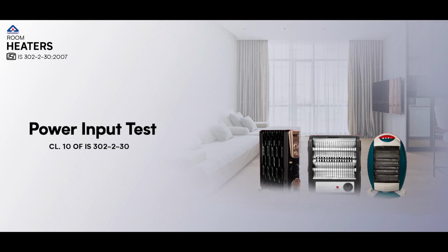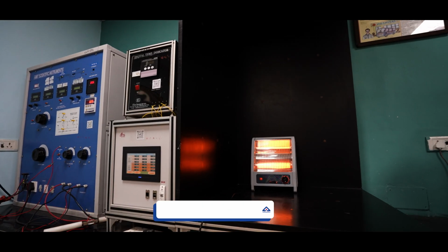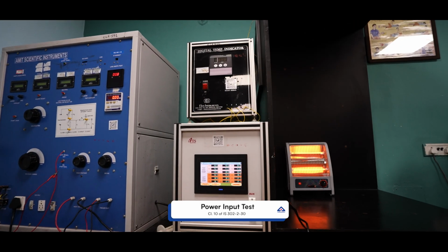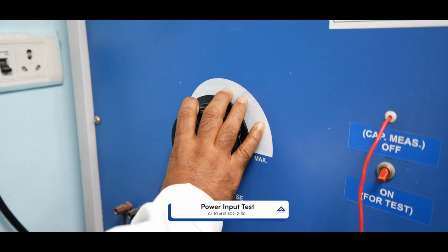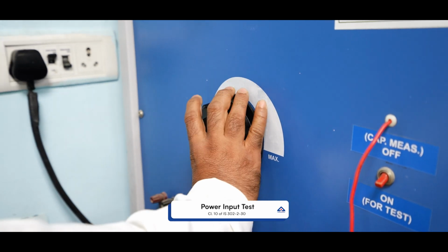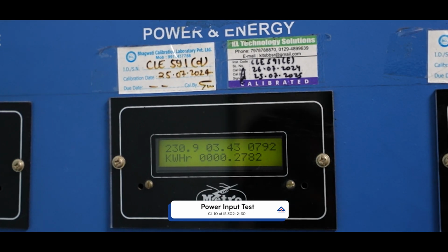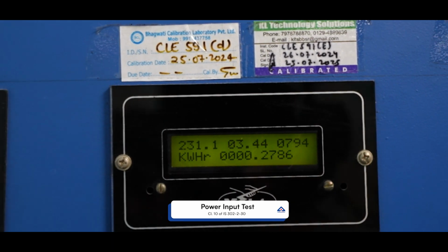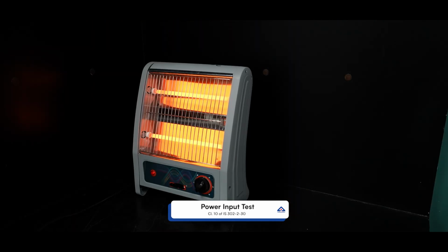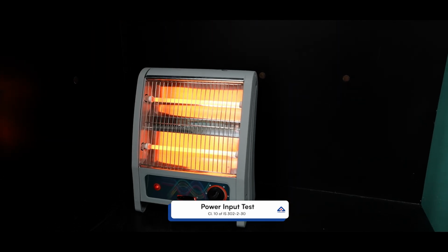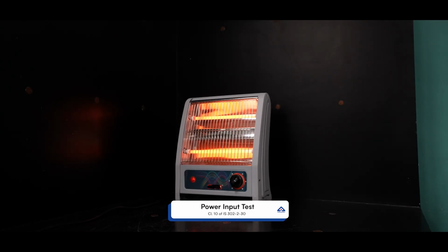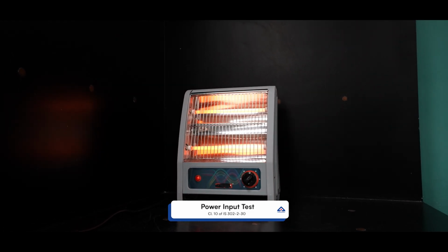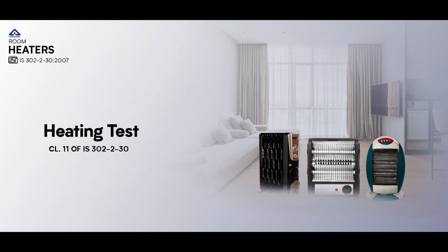Power input test. Next, we test the power input, which tells us how much electricity the heater consumes during normal operation. This is a critical measure of energy efficiency. A multifunction panel and wattmeter are used to measure power input, ensuring that the heater uses energy efficiently while providing the necessary warmth. By assessing the power consumption, we can help reduce utility costs and ensure that manufacturers meet the required performance standards.